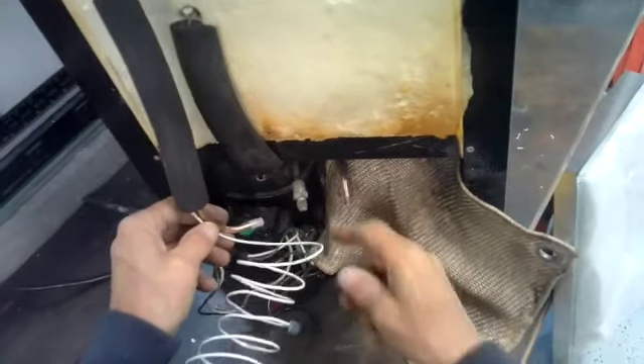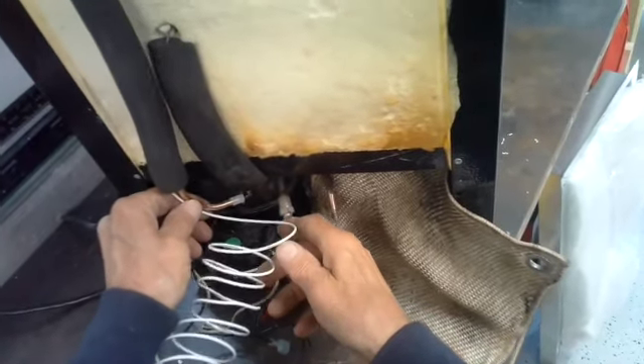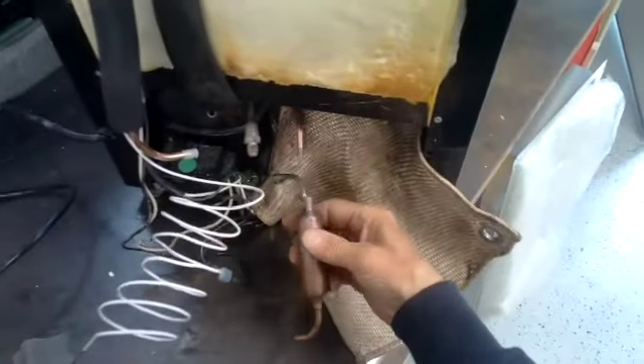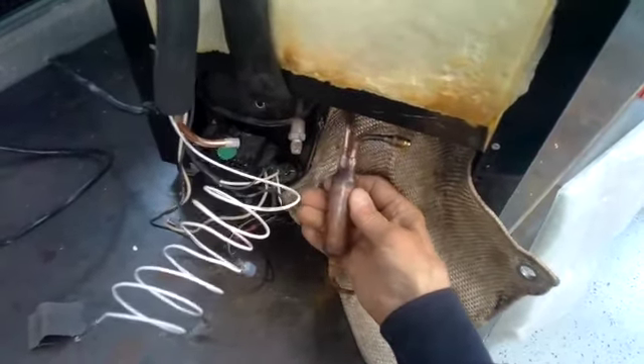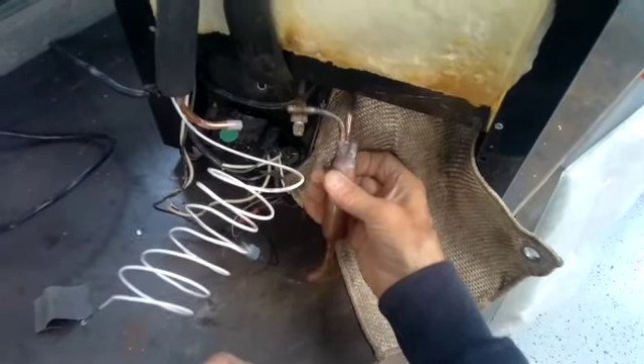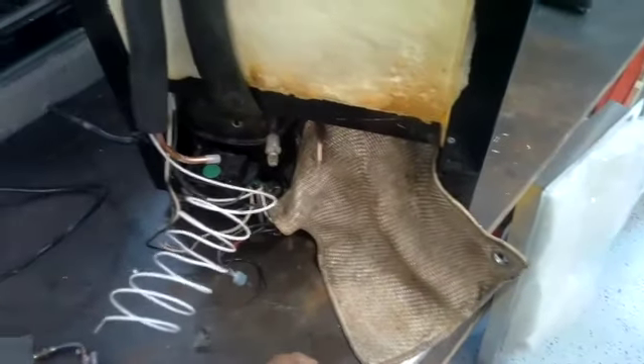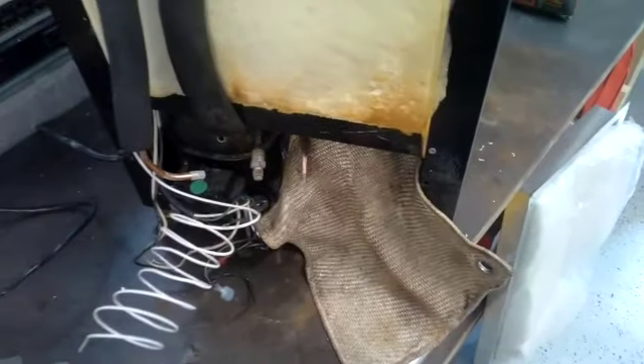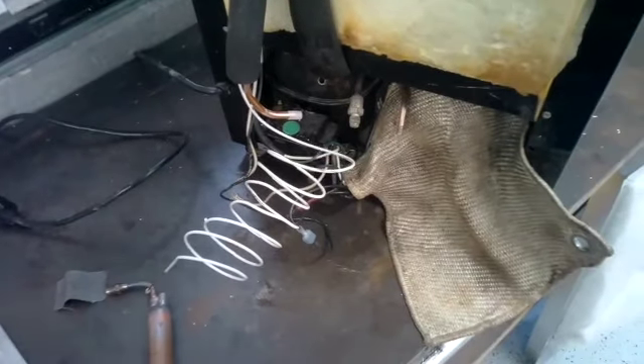Okay, so now we've fished the suction line through and the heat exchanger. We put the insulation on here and we bent it to give us a little bit more room down here. We're going to sweat the suction line into the compressor right there, and then we have a new dryer that we're going to put in right here, sweat that all in, and then we'll check it for leaks and pull a vacuum and get this baby up and running. So let's do that.